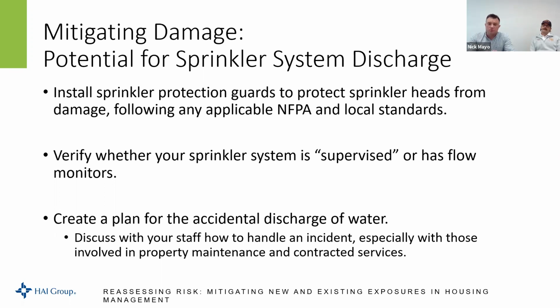Verifying whether your sprinkler system is supervised or has flow monitors is extremely important. When we say supervised, that means that the water flow within the sprinkler system either reports to a central monitoring station or a local monitoring station that would dispatch emergency apparatus. So making sure that the fire alarm system is tested regularly, inspected, and operates as it should is extremely important. Because whether it's an activated water flow alarm due to a discharge of a sprinkler head or a bump in system pressure, we still want to go out there as fire department representatives to make sure that everything's okay. And then obviously if water's flowing for an activated sprinkler head due to a fire, we want to get there as soon as possible. And the only way we know that water is flowing is through that supervision of that alarm system.